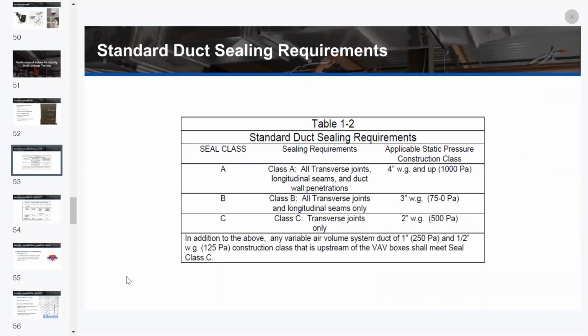So, standard duct sealant requirements: SMACNA's Table 1-2 shows the different seal classes A, B, and C. C is transverse joints only, B is transverse joints and longitudinal seams, and seal class A is all transverse joints, longitudinal seams, and any duct wall penetrations. The requirement for class A is 4 inches of water gauge and up. However, what we've been seeing, and you probably have been seeing as well, is that even in low pressure duct systems, they want a seal class A.